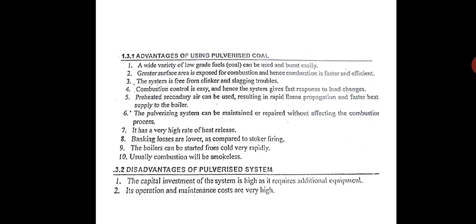The only disadvantage is that because the coal is pulverized, the capital investment of the system is high and it requires additional equipment for pulverization, and its operation and maintenance costs are also very high. It also produces fly ash and dust, because the coal is very fine. Nowadays pollution control norms are very stringent, so you require fly ash removal equipment like ESP, electrostatic precipitators. The government of India, the pollution control board, has made it mandatory to have these ESPs.